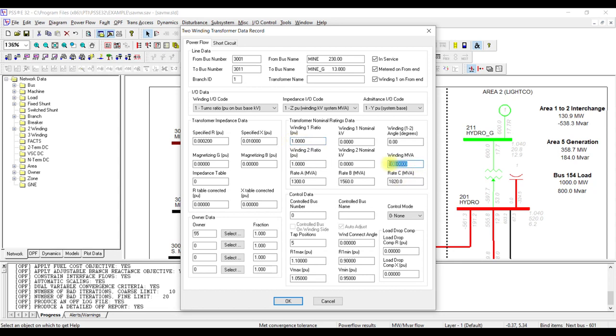The winding MVA can be considered as the base MVA. Then there is Rate A, Rate B, and Rate C — these are the thermal ratings. For a transformer or any transmission line you can model different ratings. Rate A is the normal rating (e.g., 100%), Rate B can be the emergency rating at 120% of normal capacity, and Rate C can be the maximum possible emergency rating at perhaps 150%. You would enter the actual MVA multiplied by 1.5 for Rate C.